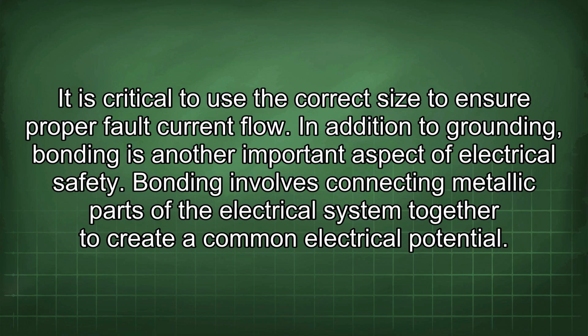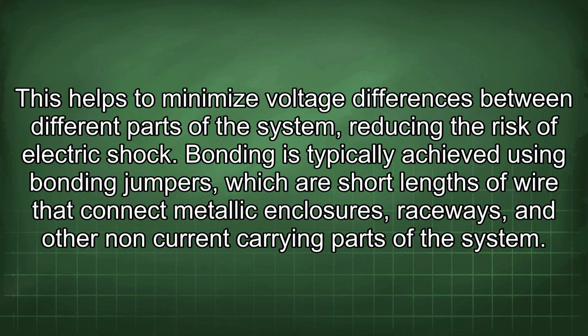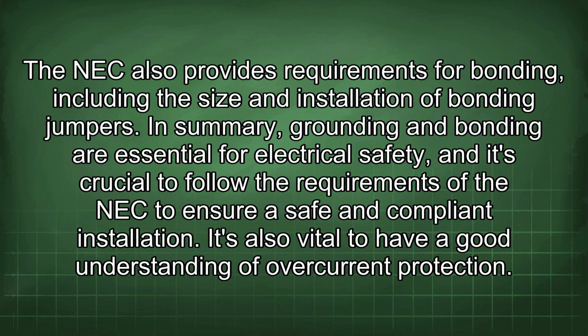In addition to grounding, bonding is another important aspect of electrical safety. Bonding involves connecting metallic parts of the electrical system together to create a common electrical potential. This helps to minimize voltage differences between different parts of the system, reducing the risk of electric shock. Bonding is typically achieved using bonding jumpers, which are short lengths of wire that connect metallic enclosures, raceways, and other non-current carrying parts of the system. The NEC also provides requirements for bonding, including the size and installation of bonding jumpers. In summary, grounding and bonding are essential for electrical safety, and it's crucial to follow the requirements of the NEC to ensure a safe and compliant installation.